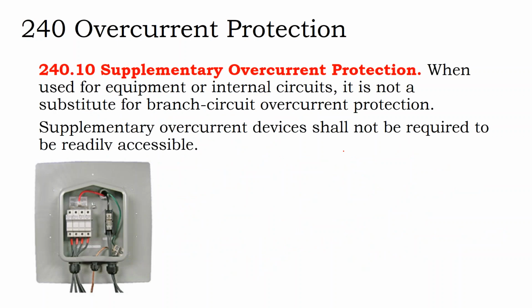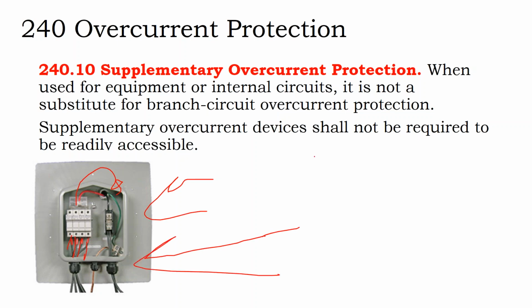Now these fuses and breakers, you may be required to have a main overcurrent protection device, but then you'll find that there are fuses and other overcurrent protection devices in your system that might do other things. Like if you want to do a combined run where you have multiple circuits being combined into one wire, maybe that occurs in a box in the roof, maybe that occurs inside your inverter itself.